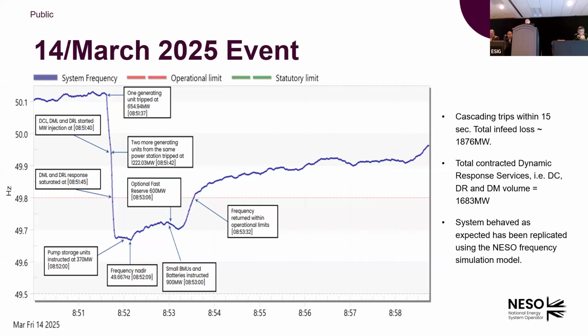That's when we had a blackout in the London area. The amount of generation loss is actually quite similar, all around the 2 gigawatt range. But you can see this time the frequency behaves much better. The main reason, because we only have one grid forming battery, is not related to the grid forming battery. The main reason is how we have changed our frequency response product.